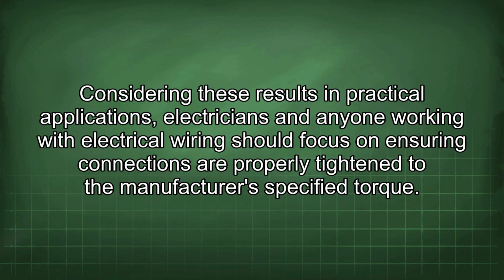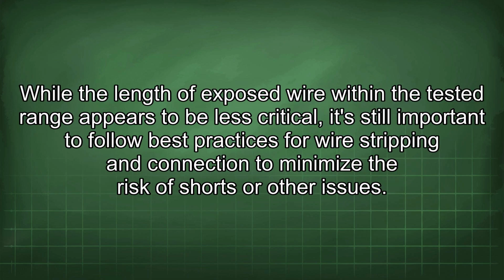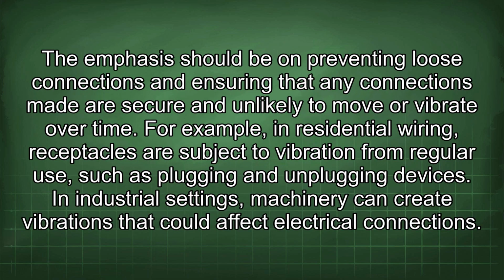Considering these results in practical applications, electricians and anyone working with electrical wiring should focus on ensuring connections are properly tightened to the manufacturer's specified torque. While the length of exposed wire within the tested range appears to be less critical, it's still important to follow best practices for wire stripping and connection to minimize the risk of shorts or other issues.